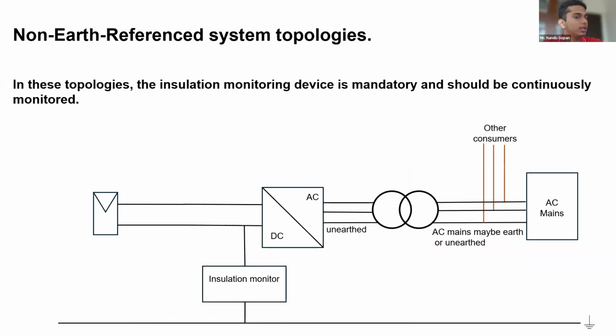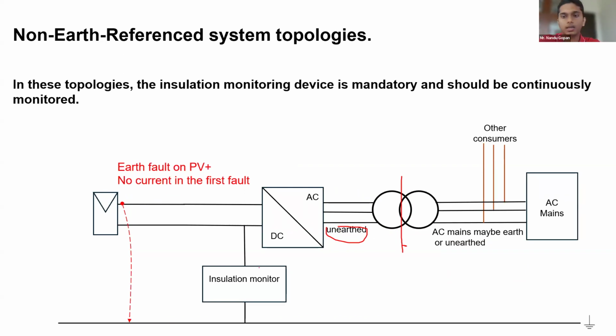Now, the third type of topology is the non-earthed system. In a non-earthed system topology, it won't be earthed; it will be unearthed till here. There won't be any system referencing conductor till this transformer. So in that case, if there's a fault on the PV positive, there won't be any return current. It will be completely an IT source. And one more thing to notice, the insulation monitoring device will be working 24 by 7. If there is any weak insulation, this insulation monitoring device will detect it, and it should inform the owner that there is weak insulation, and they are supposed to rectify it as soon as possible.